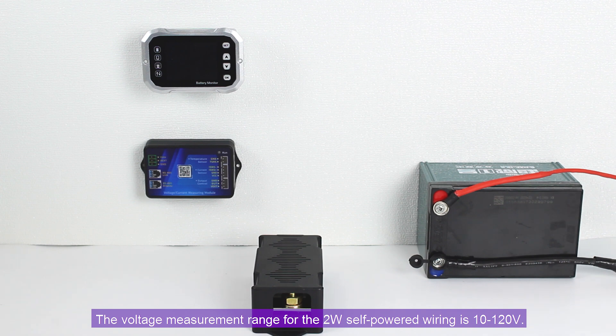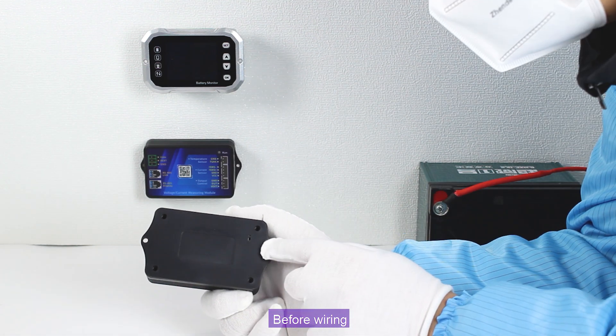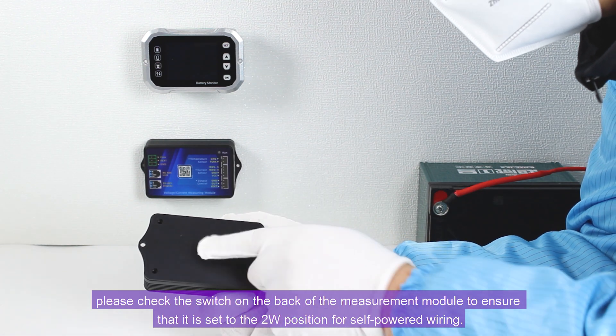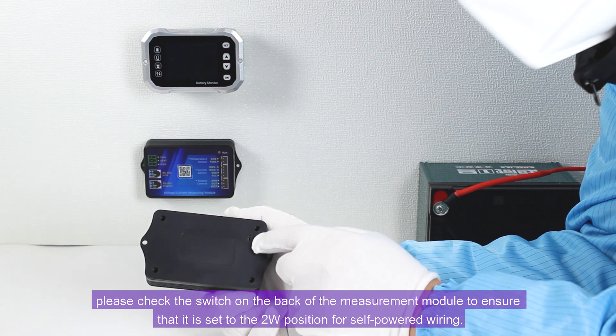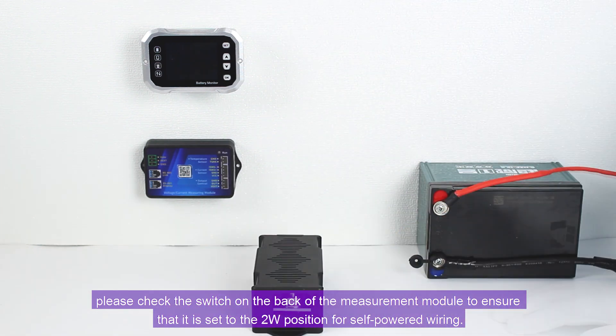The voltage measurement range for the 2W self-powered wiring is 10 to 120 volts. Before wiring, please check the switch on the back of the measurement module to ensure that it is set to the 2W position for self-powered wiring.